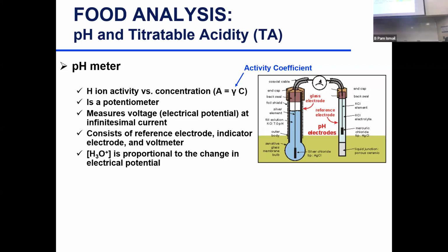Infinitesimal? What did you say? What is that difference? So there is a sample electrode and there's the reference electrode that has a reference solution in it that will always have a constant voltage. You always have to have your reference. Some new pH meters have the reference and the sample electrode in one compartment. Some old ones you need to put both in your sample.